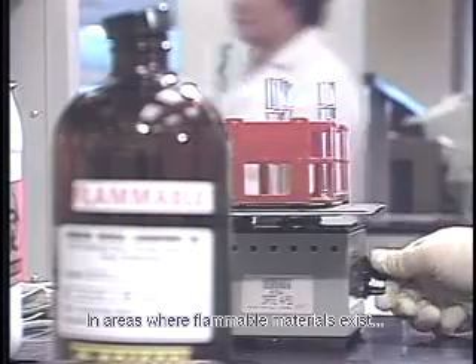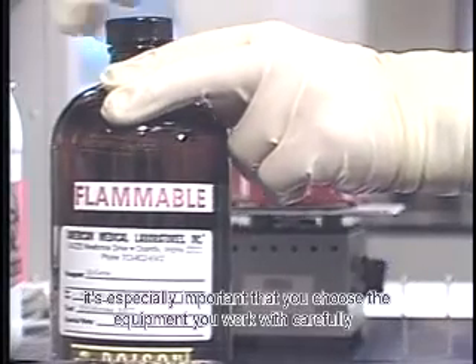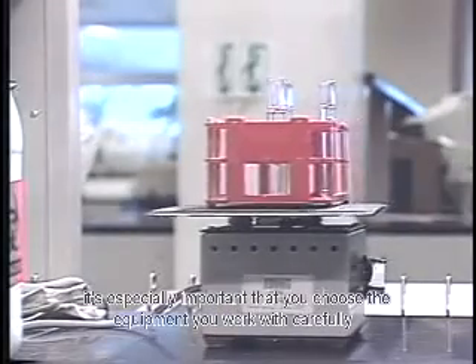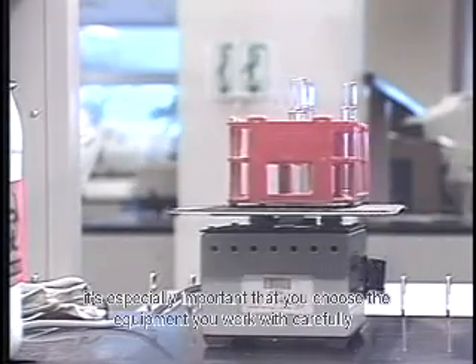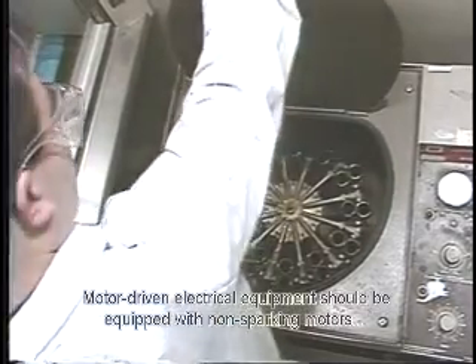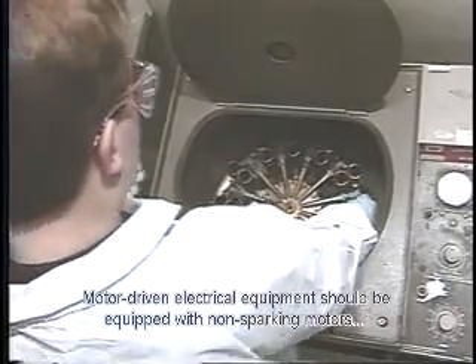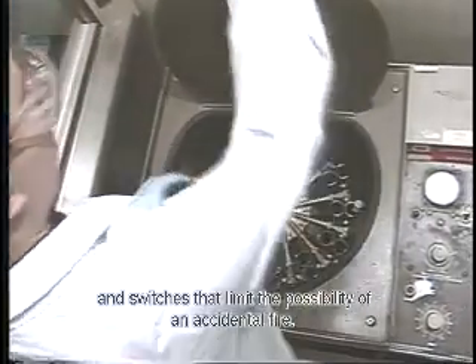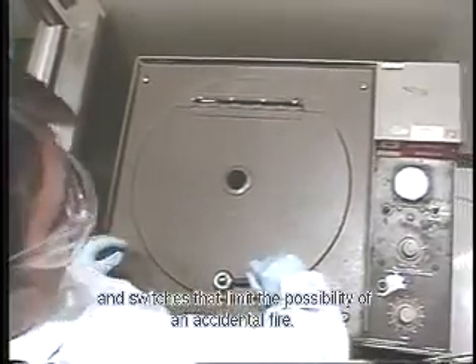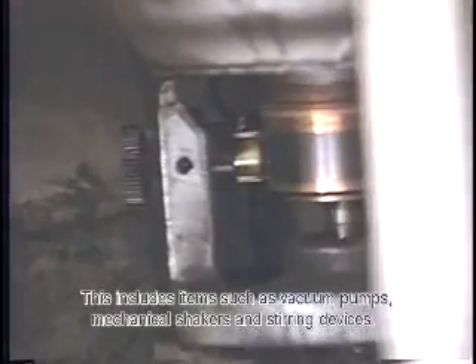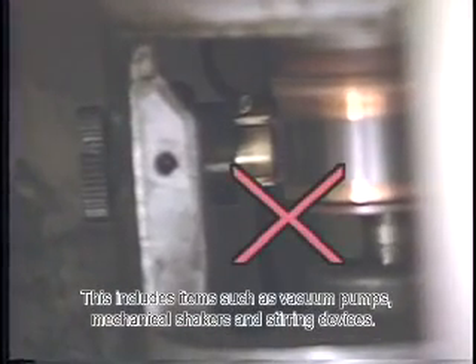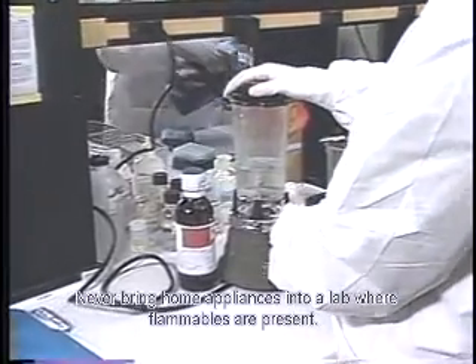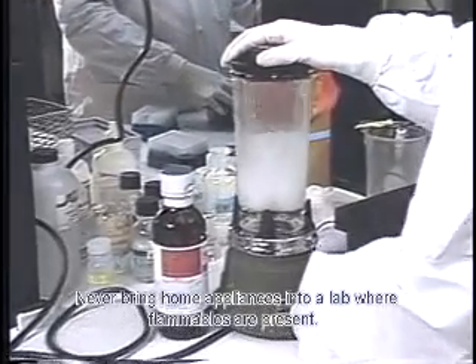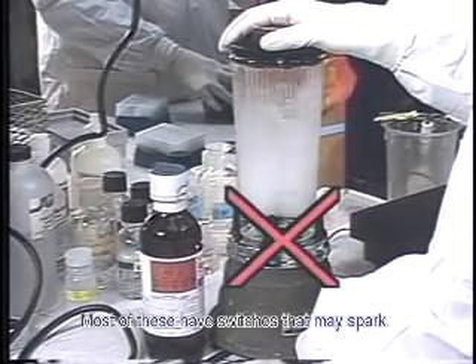In areas where flammable materials exist, it is especially important that you choose the equipment you work with carefully. Motor-driven electrical equipment should be equipped with non-sparking motors and switches that limit the possibility of an accidental fire. This includes items such as vacuum pumps, mechanical shakers, and stirring devices. Never bring home appliances into a lab where flammables are present. Most of these have switches that may spark.